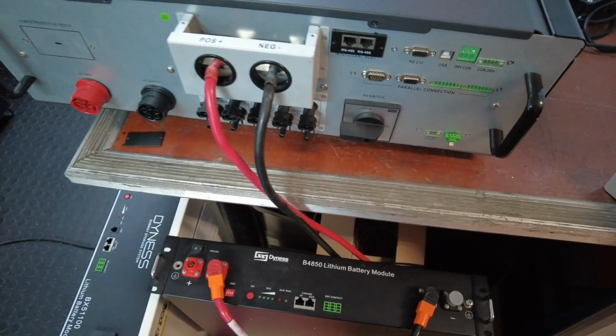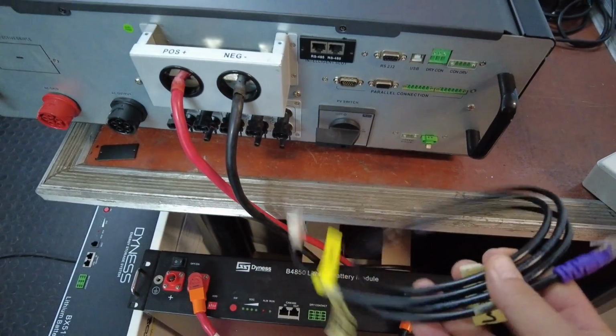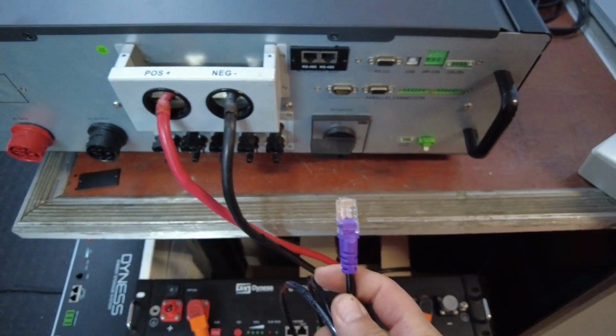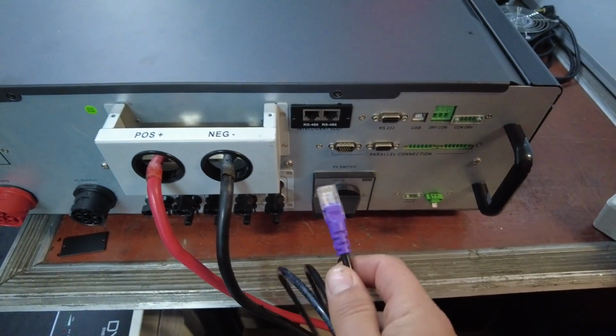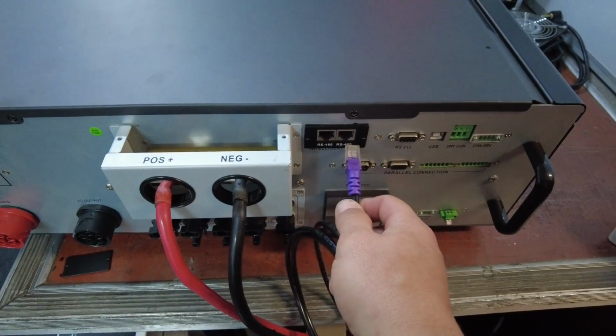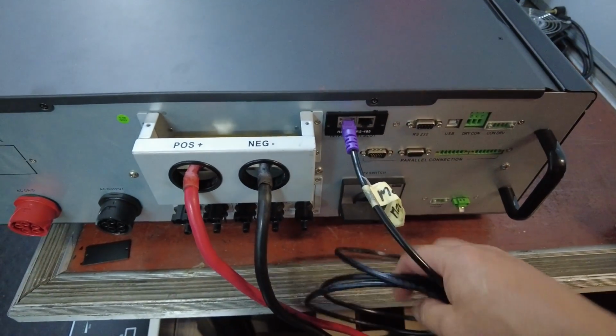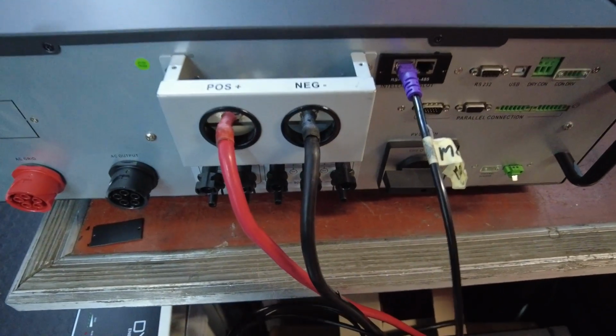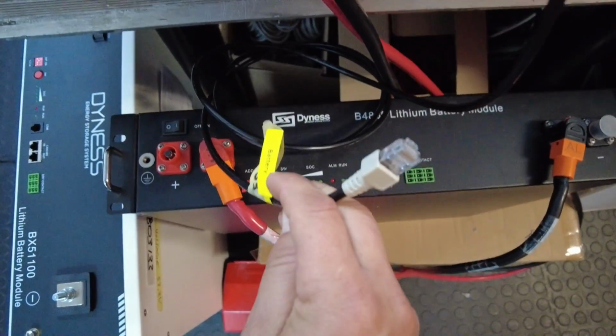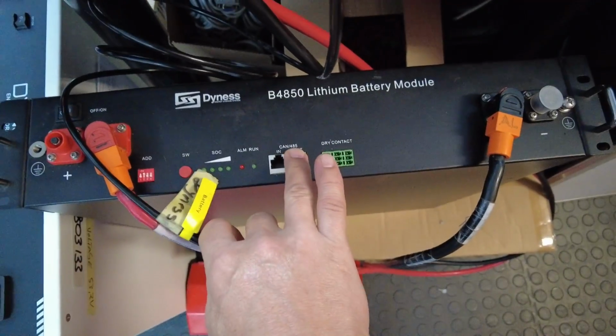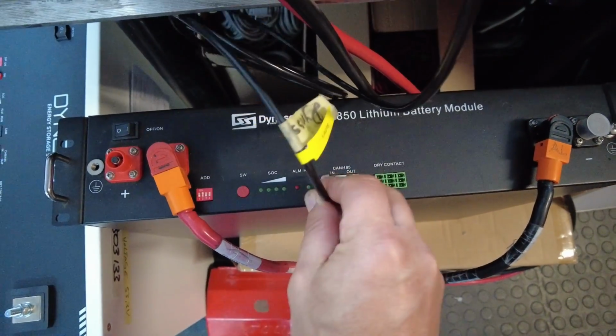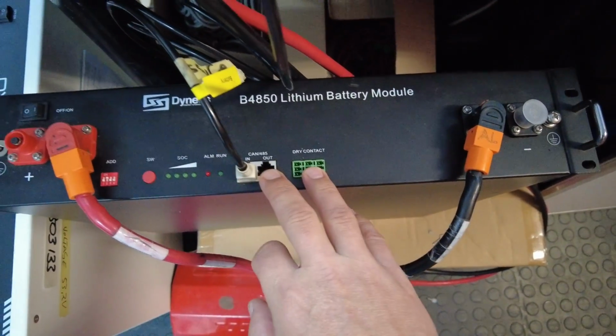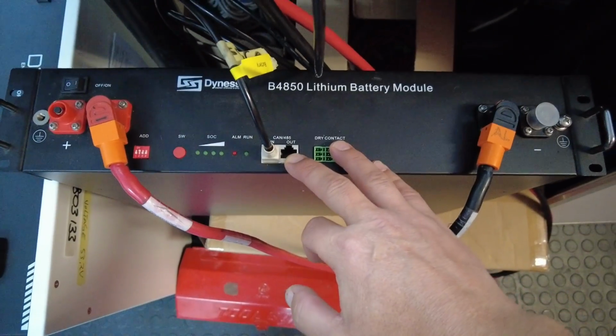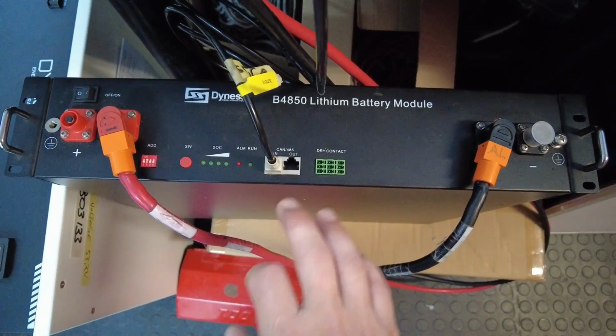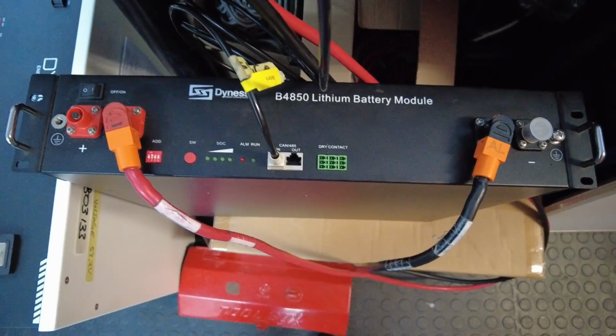Okay, the Modbus card is installed, dip settings are set, and the cable is made. Let's hook everything up. As mentioned before, the purple side of the cable I made is for the inverter, and that can go to either one of these two RS485 ports. Doesn't matter which one you use. Then for the battery side, I've crimped the grey plug. That will go to the CAN 485 in port. As for your slave batteries, once you have additional batteries added on, you will run a normal networking cable from the out to the next battery's in, and then from that battery's out to the next battery's in, and so forth.